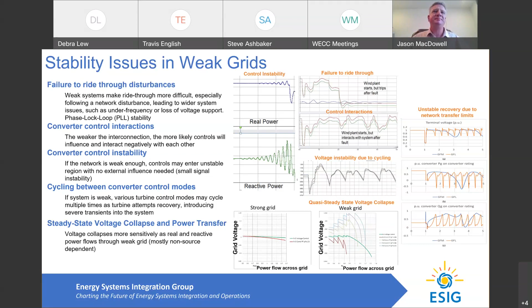To wrap up, a couple more slides from the article, looking at some of the voltage and angle stability risks we have to be cognizant of. In highly interconnected systems, those voltage and angle stability risks tend to be localized, where local electrical disturbances may risk a pocket of inverter-based resources going unstable, potentially causing voltage and frequency issues at that local interface.